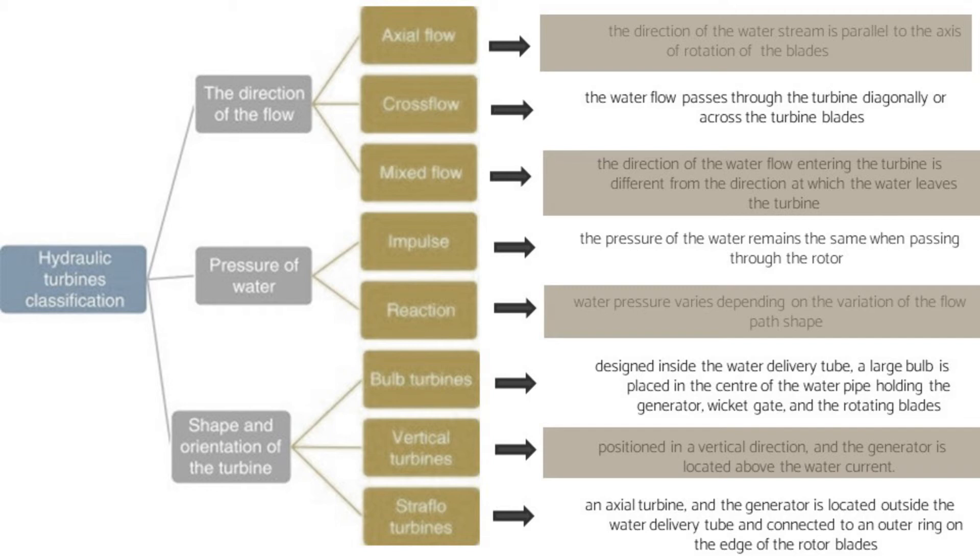For the shape and orientation of the turbine, we have bulb turbines, vertical turbines, and Straflo turbines. Bulb turbines are designed inside the water delivery tube. A large bulb is placed in the center of the water pipe holding the generator with guide vanes and rotating blades. For vertical turbines, they are positioned in vertical direction and the generator is located above the water current. For axial turbines, the generator is located outside the water delivery tube and connected to an outer ring on the edge of the rotor blades.